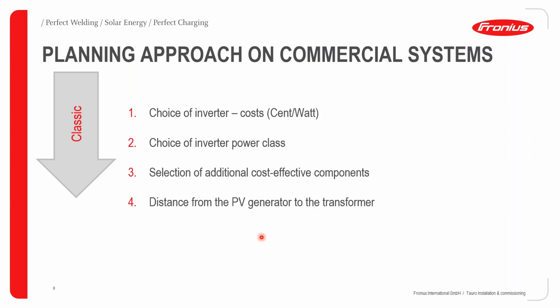So that affects, of course, the design around DC and AC cabling and the components in between. So this is the classic approach, but with the Tauro, we want to approach it from a different direction. We want to ask, what is the distance of the PV generator to the transformer or the point of interaction or the feed-in point? That becomes one of the biggest advantages that the Tauro is going to offer you, as you're going to see later as we progress. And then all these other points will be considered based on your design around the distances involved.